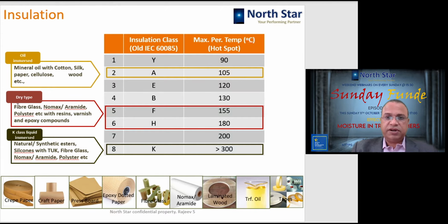Second, we all know dry type transformers are there, which do not have any liquid in them, so that's why they are called dry. And there are two thermal classes: class F and class H. After that, there are now K class liquid immersed transformers also available. They are much more capable as far as thermal capability is concerned, because they can work at a temperature of more than 300 degrees centigrade. These typically employ K class liquids, which are natural and synthetic ester, in combination with either of these solid insulations.